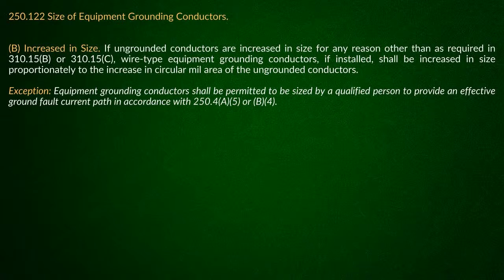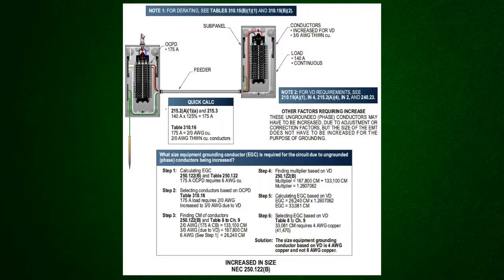If you have to increase those ungrounded phase conductors for any reason, then it tells you that the equipment grounding conductor will have to be increased in size proportionally to the increase in circular mil area of the ungrounded phase conductor. So what I did, I don't even know if anybody else actually shows this in their publications or not. Let me look at it real close. Okay, no, they don't. But when you look at 250.122(B), it talks about an increase in size.